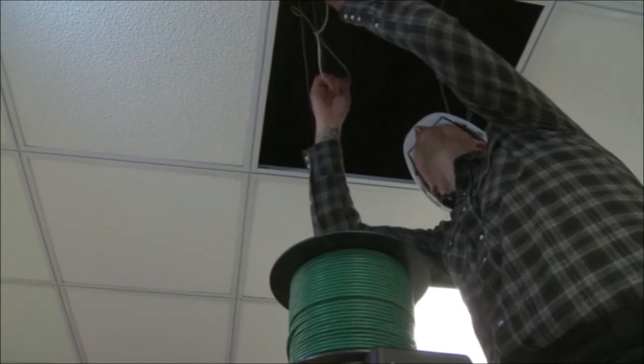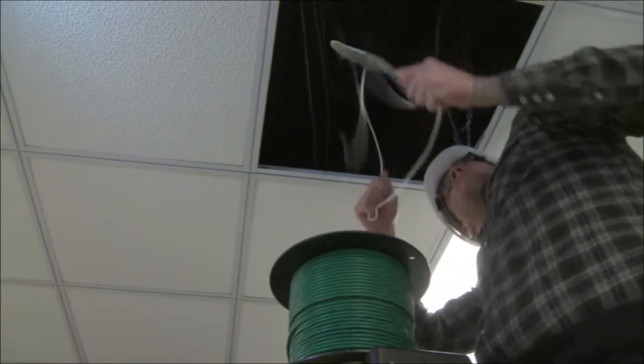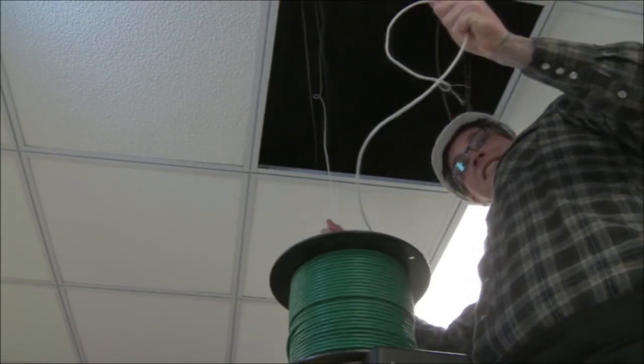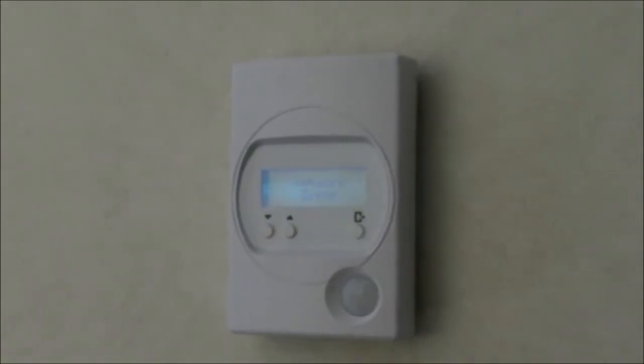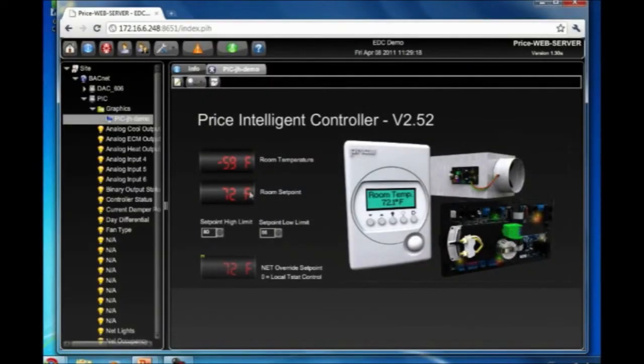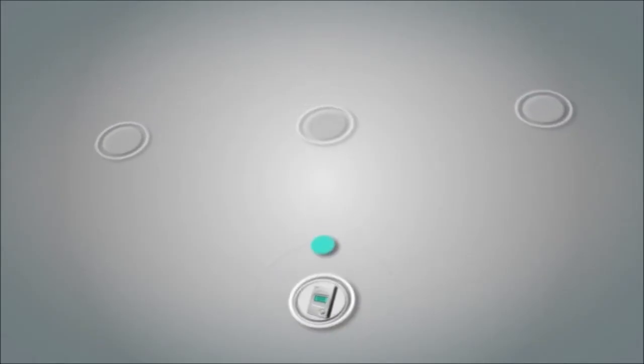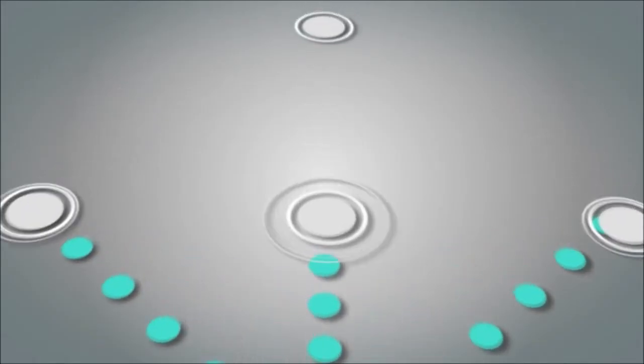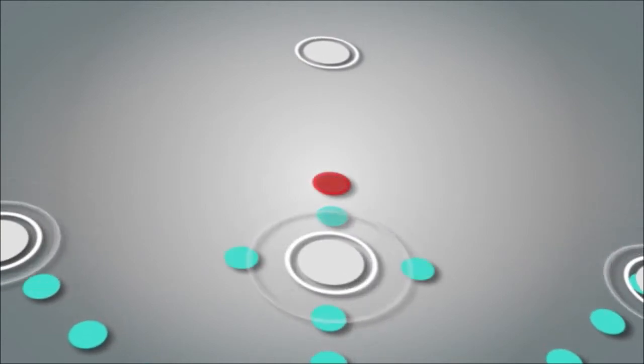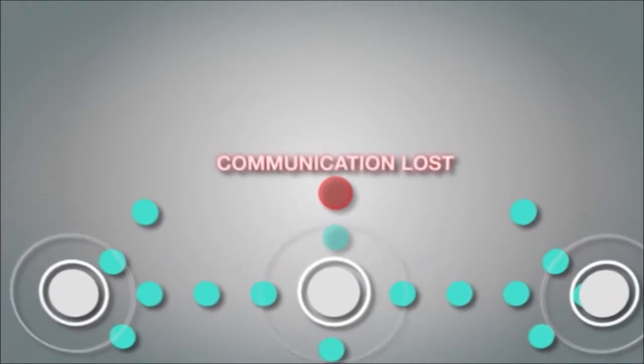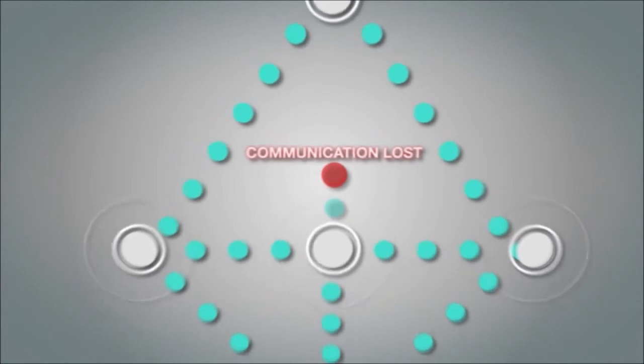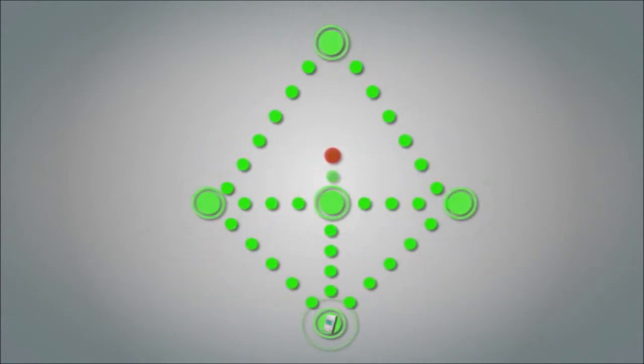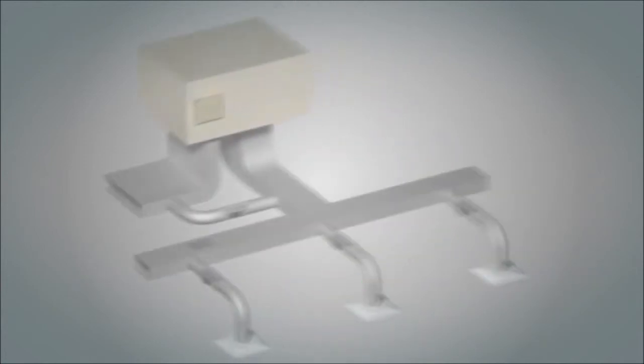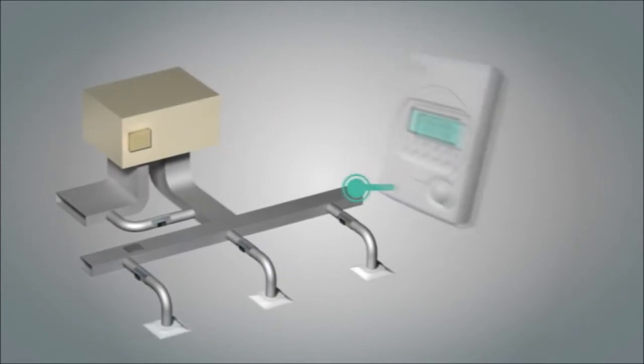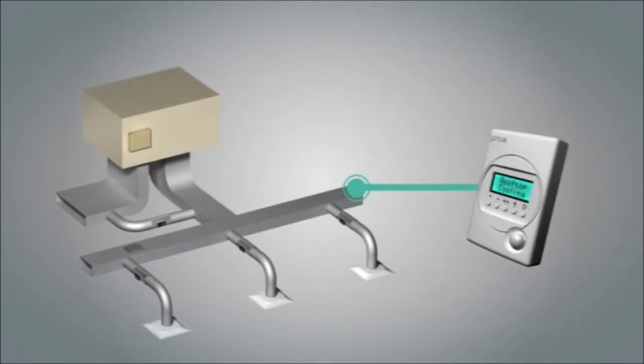If for any reason network communication is lost with a small number of zones, the fault tolerance built into the PRTU will notify the user and remove the influence of the missing zones from the system. This allows the PRTU to continue operating and satisfying the majority demand. If communication is lost with a large number of zones, the PRTU can automatically revert to a standalone mode, wherein the rooftop unit is controlled using the traditional single thermostat architecture.